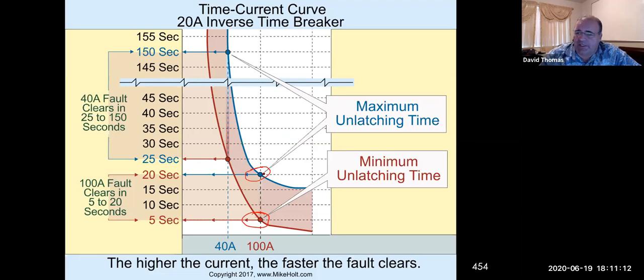So in here we have a maximum unlatching time for the breaker at 100 amps. Okay, so that's 100%, 500%, right? If it's a 20 amp breaker, the 20 amp breaker at 500% will unlatch between 5 to 20 seconds. That's actually a very slow time, by the way. Most of them will trip faster than that.